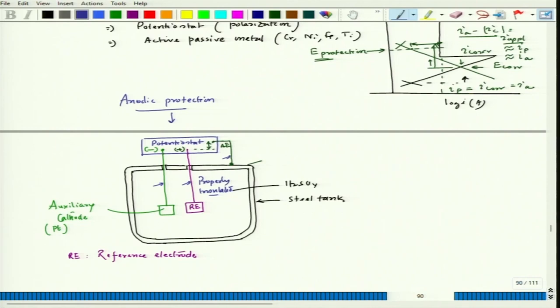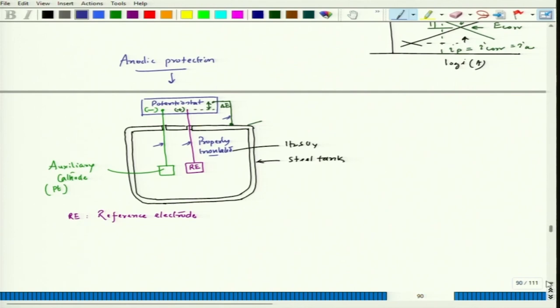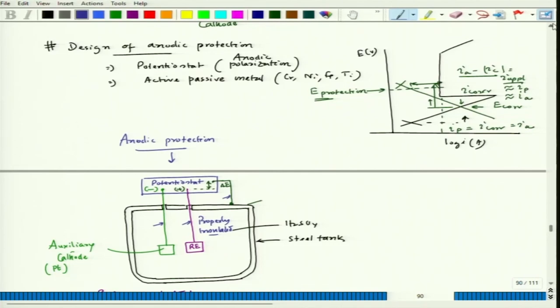Looking at some advantages of anodic protection: though the initial current requirement is very high and the setup is a bit complicated with high initial installation cost, once E protection is achieved, it can be maintained with a very tiny current density. The cost of maintenance is very low. This is not true for ICCP or sacrificial anode, where anodes must be replaced periodically — for example, high silicon steel anodes are brittle and can break during transportation.